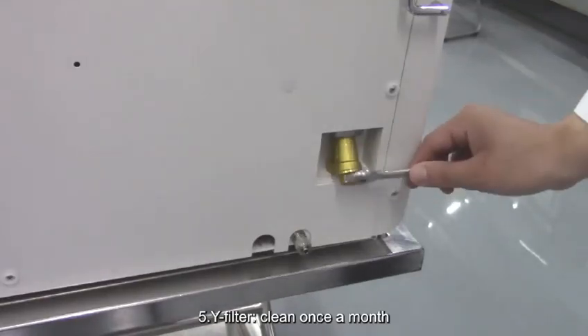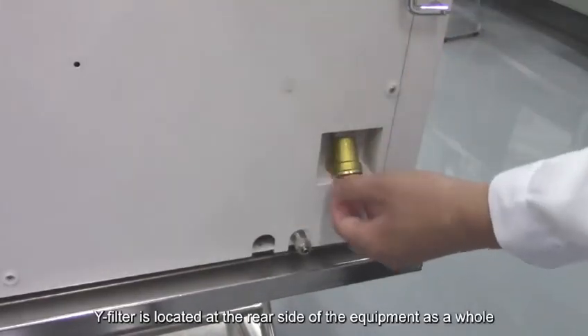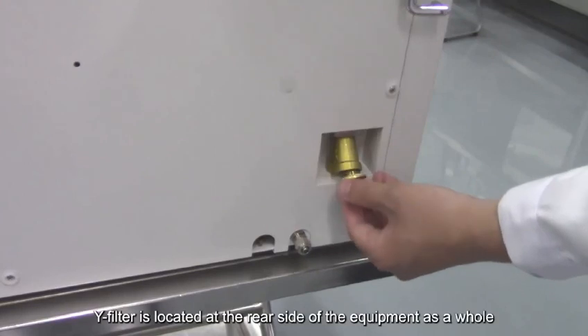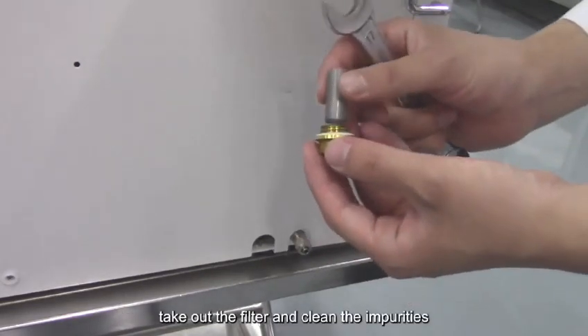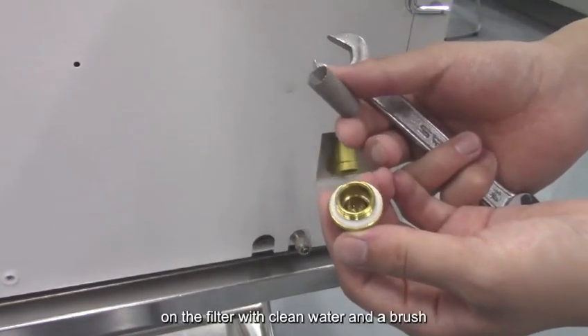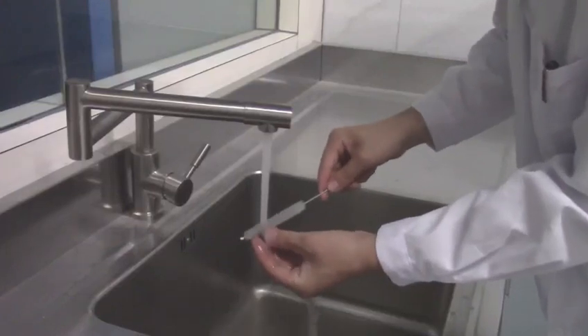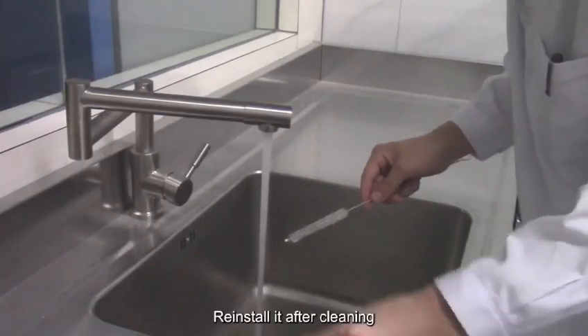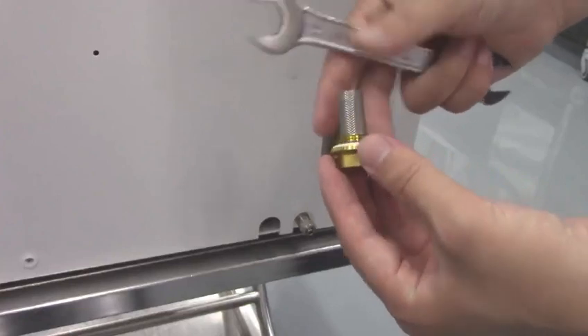5. Y filter. Clean once a month. The Y filter is located at the rear side of the equipment as a whole. After removing the nut, take out the filter and clean the impurities on the filter with clean water and a brush. Reinstall it after cleaning.